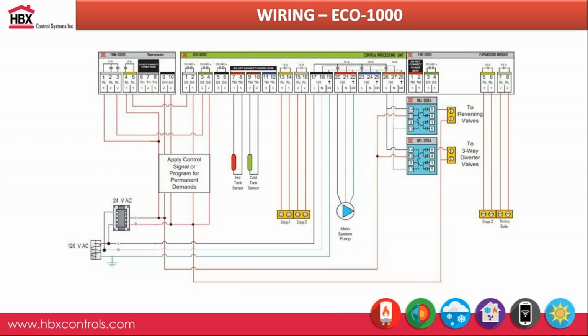So if you're ever not getting any heating or cooling within your application, always make sure that when you look at the controller, you see an HD or CD. If you don't see those, that means we don't need heating or cooling in those places, and that's why your heat pumps or your chillers are not operating at the present time. That's one of the biggest calls that we get in tech support: the controller is just not getting those demands to turn on your heat pumps.